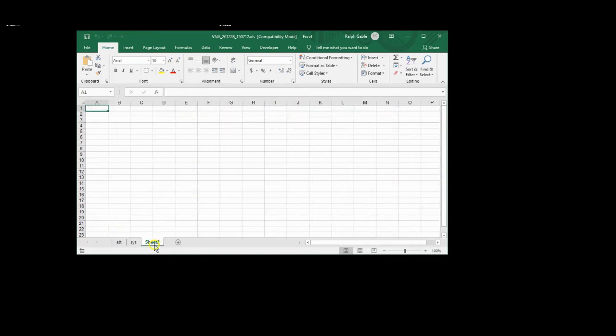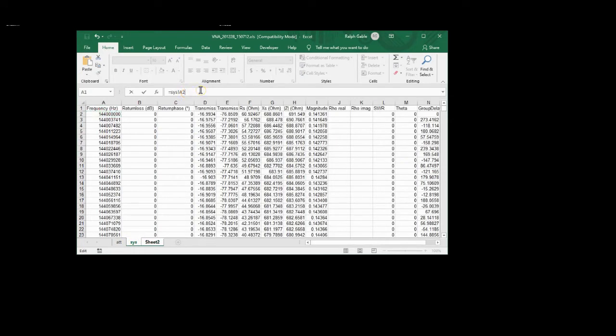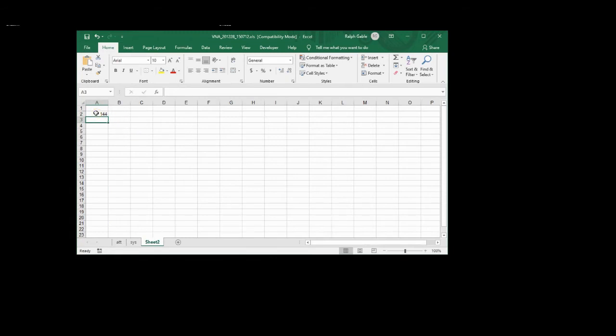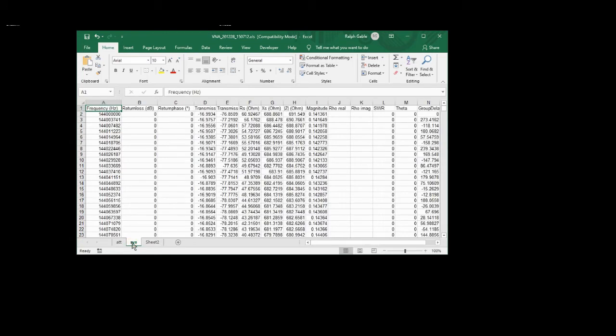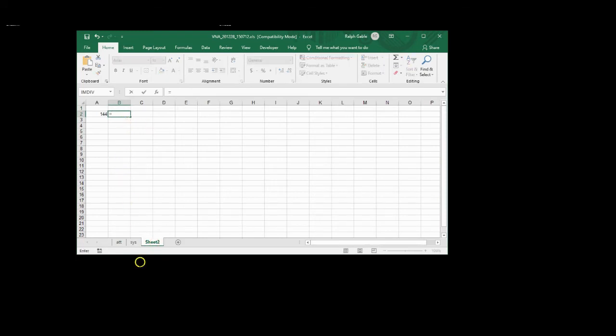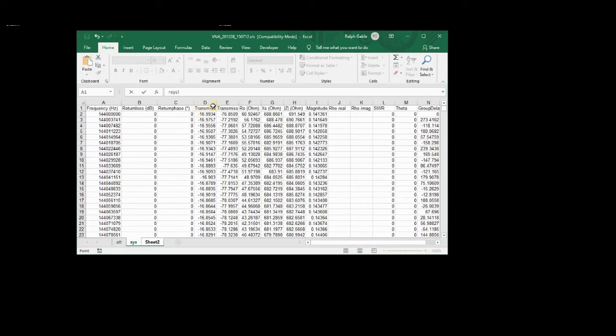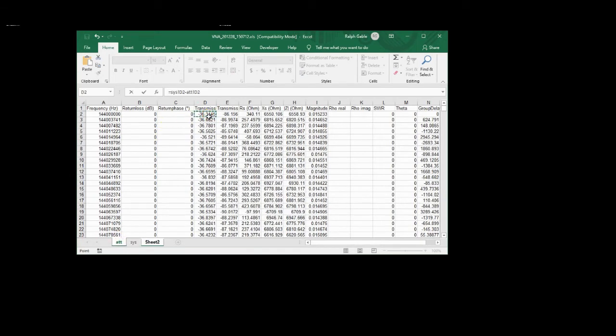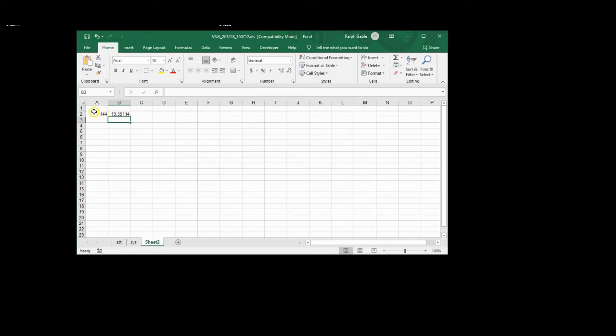And then I'm just going to create one more sheet here. So what I'm going to do here is set this equal to this sheet here, this divided by 1 million. That way I end up with megahertz here. And then this one, sys, is the entire gain, including this attenuator and everything, and we want to subtract out the attenuator. And that's just the attenuator, and it has all the same frequencies that this one has. And so we're going to say equals this one right here. See, it says transmission. We're going to take that value right there, and we are going to subtract this value right here, and that gives us the gain at that frequency.